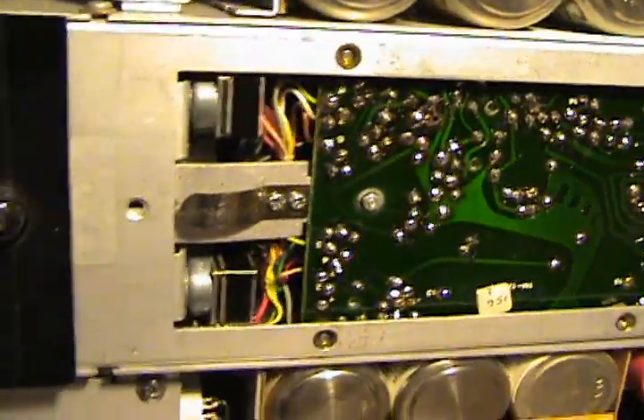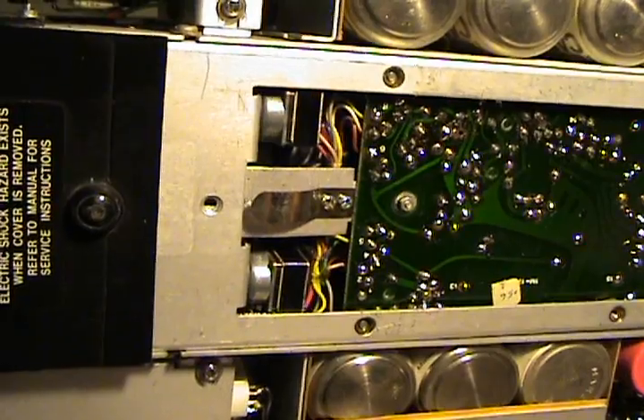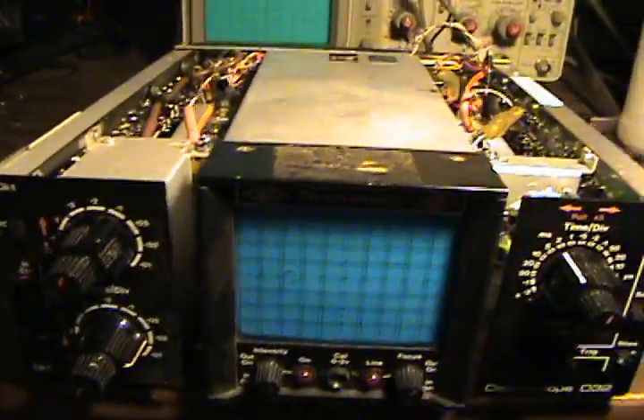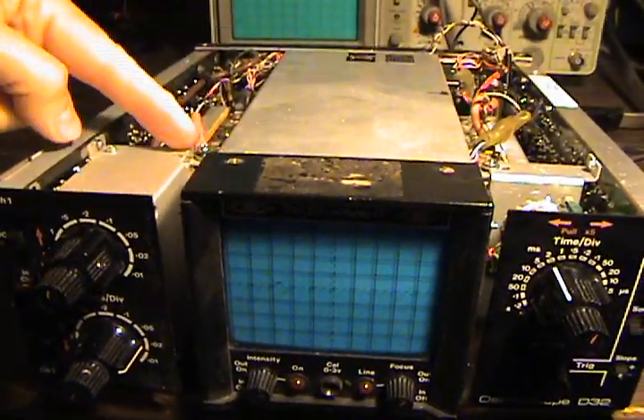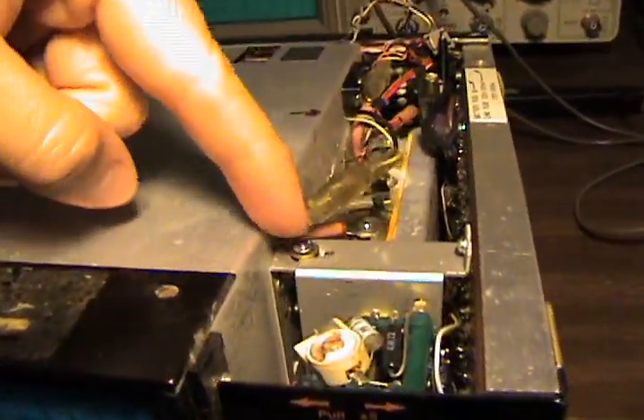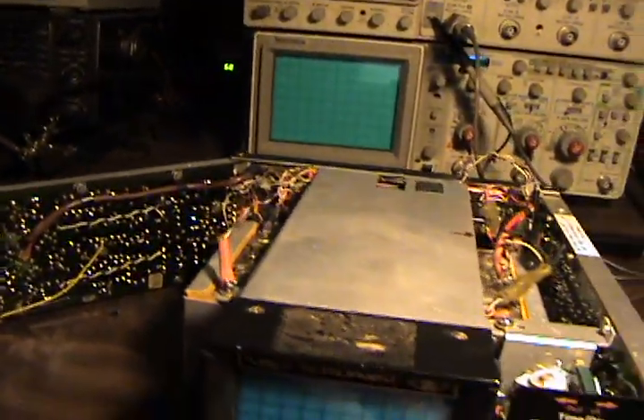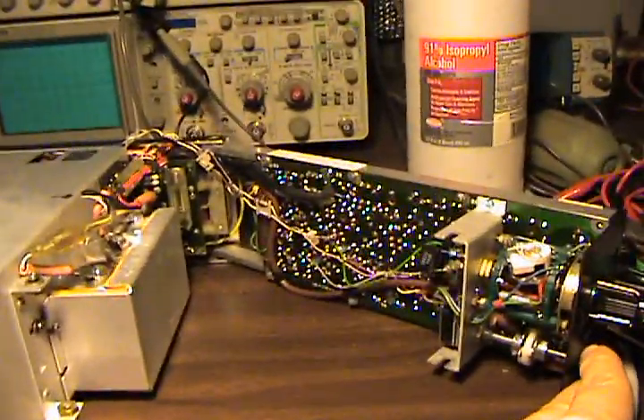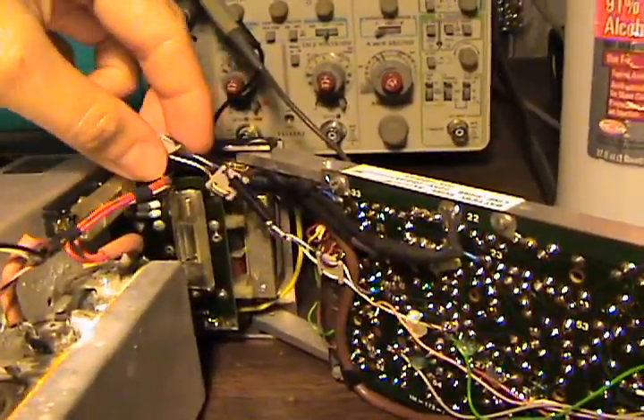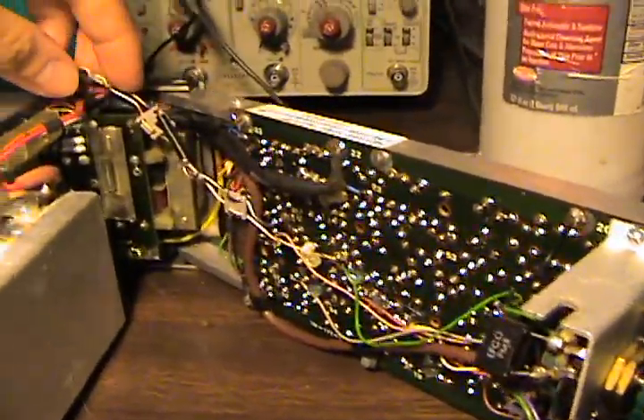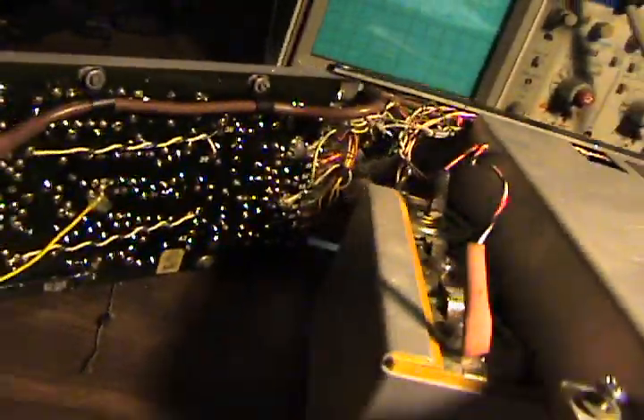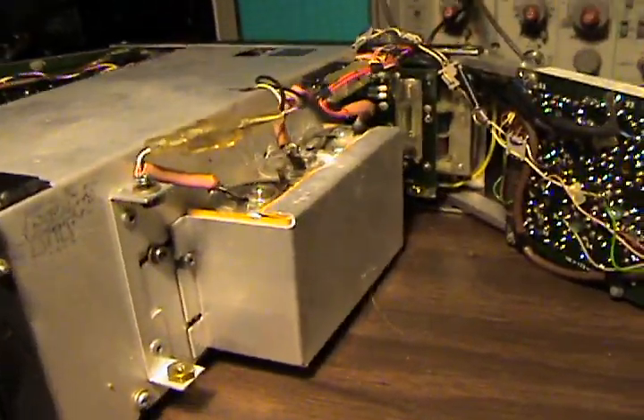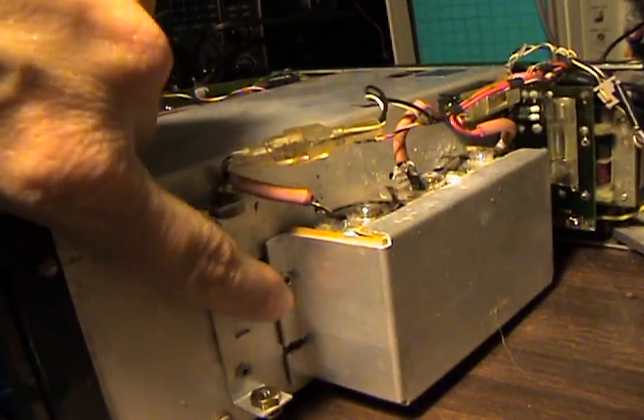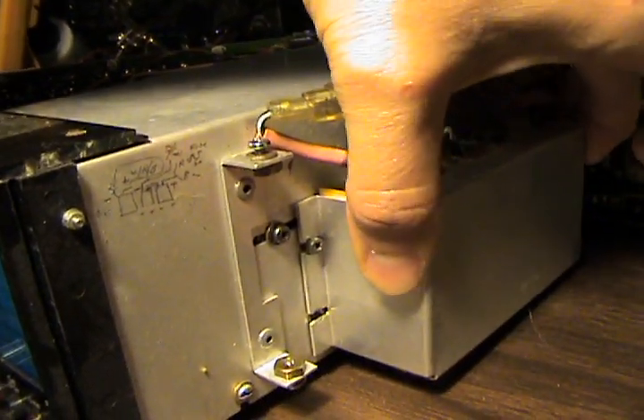Let's open up the top of it and expose the CRT and see what we can see inside of there. So here's the best thing about this little unit. You loosen this screw, there's another one on the bottom just like it, and there's another one here and another one on the bottom, and these things just swing away. They're hinged in the back with other screws. Swing them out of the way, and there's enough wire on all these harnesses to let you do that, so you can open it up, make your repairs, make your adjustments, whatever you need to do. Get to the batteries. This battery cover is just screwed in right here. You just slip that off and the batteries fall out, so you can replace them.